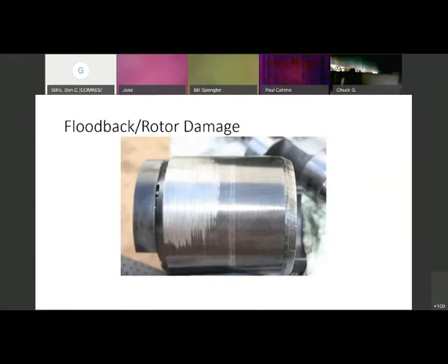So a lot of times when we get compressors back on the teardown, whether they're under warranty and maybe we've lost 1 or 2 on the same job, what you and I, or what contractors see out there, is typically marked as they take their voltmeter out and they see it as an electrical issue. But what we find when we tear them down is very interesting. I've learned a lot about this since I've been here: more times than not, it's a mechanical issue that led into an electrical issue. And these are a couple good slides that point that out very well.